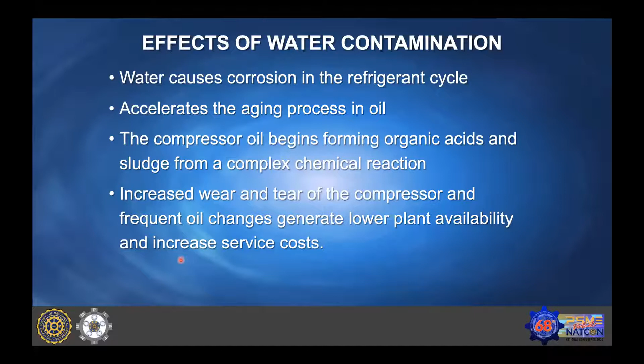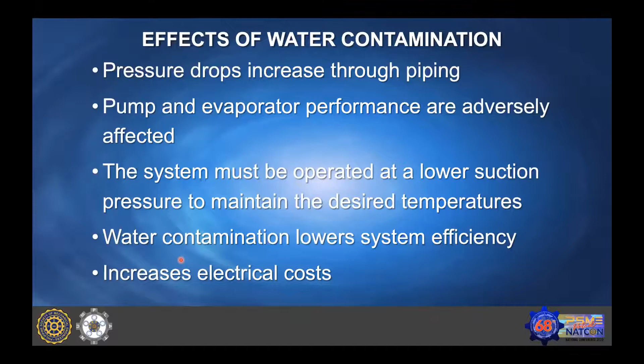As water starts accumulating, the pressure drops increase through the pipelines. Then the performance of the ammonia pump is affected. Because water accumulates on the low pressure side, evaporator performance is affected. As I've shown you in the chart, we're operating at a lower suction pressure to maintain the desired temperature. Our power requirement goes high, which lowers the system efficiency and increases the electricity cost.